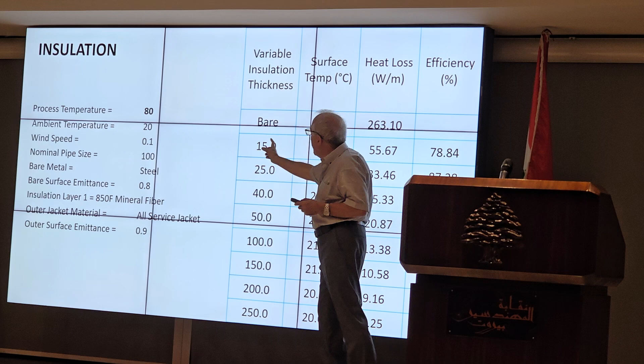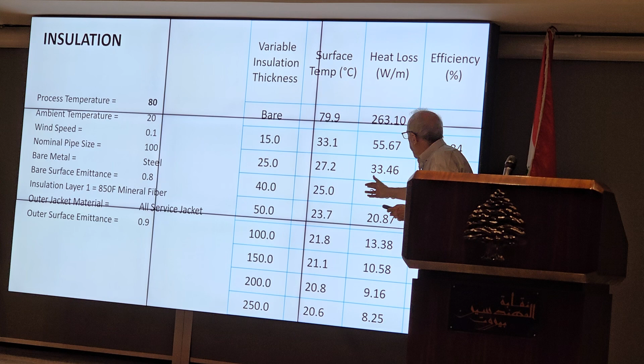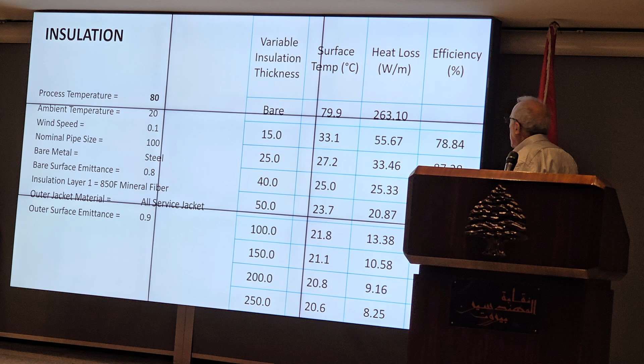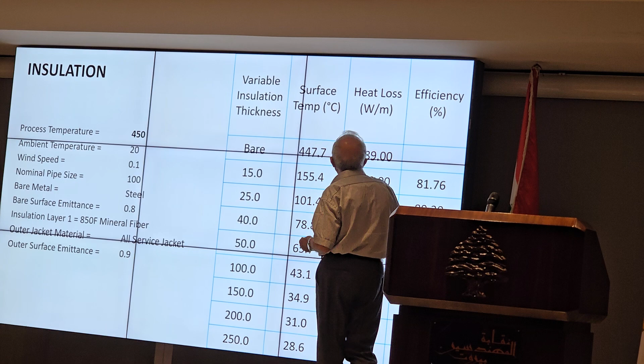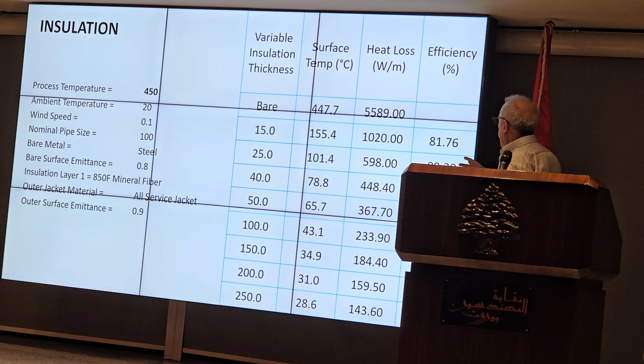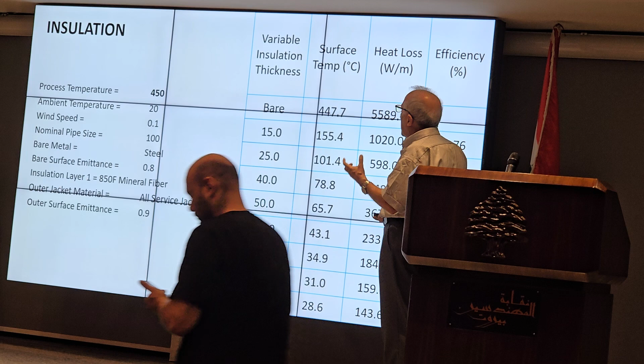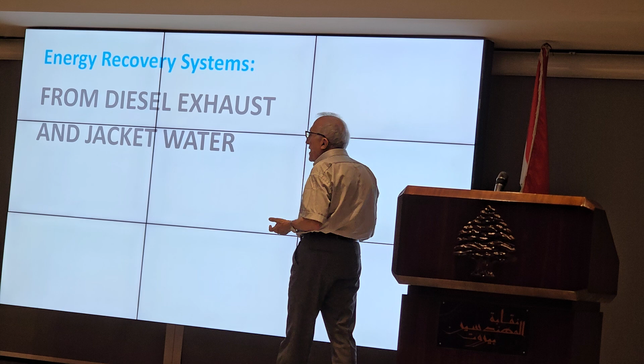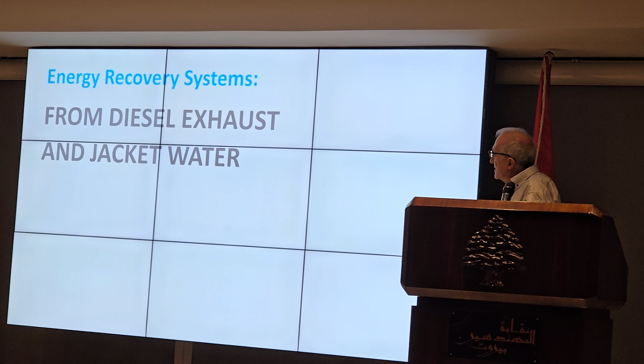If we put a 15 millimeter insulation, it drops to 55. If we go to 40 millimeter, it drops from 263 to 25. Probably a little bit acceptable. For a 450 process temperature, we can lose something like 5.6 kilowatt if it is not insulated. So this is to pinpoint how important insulation is, especially when it runs for 6,000 hours a year.